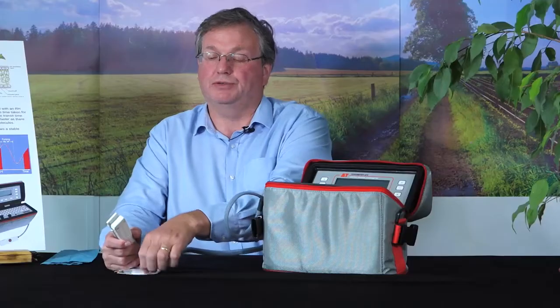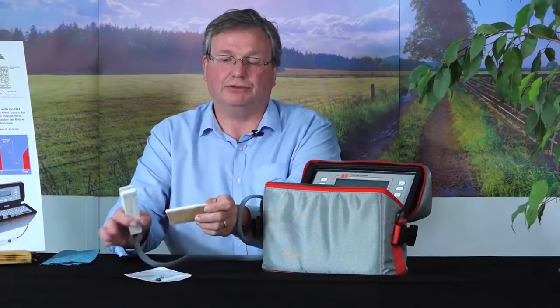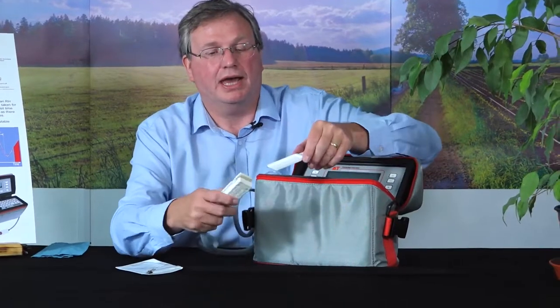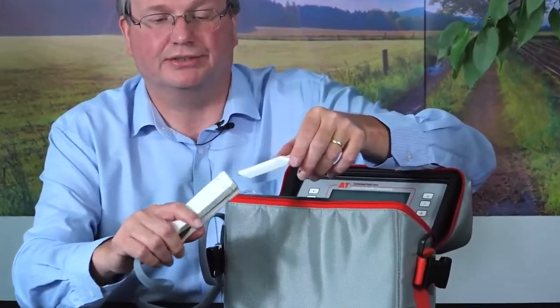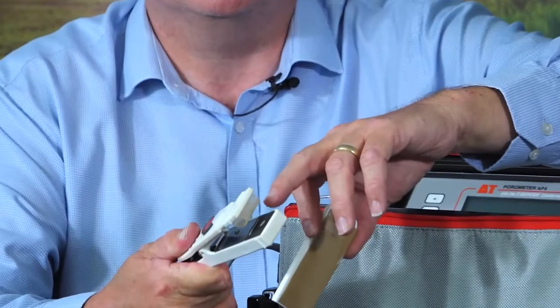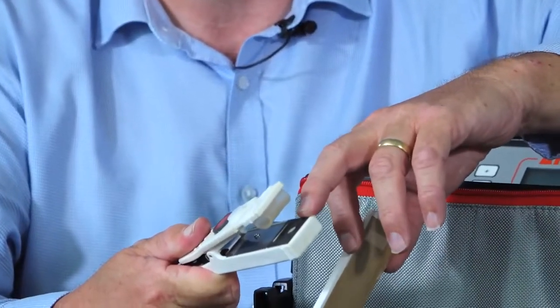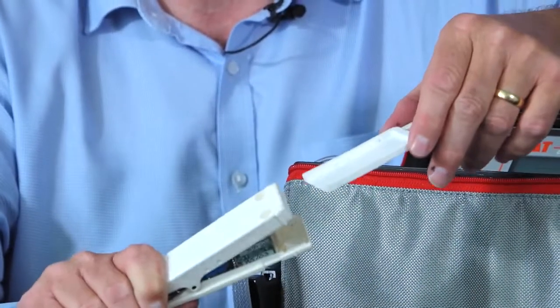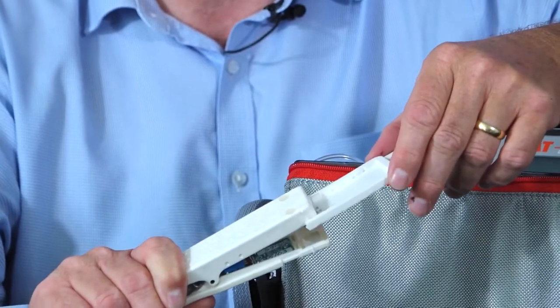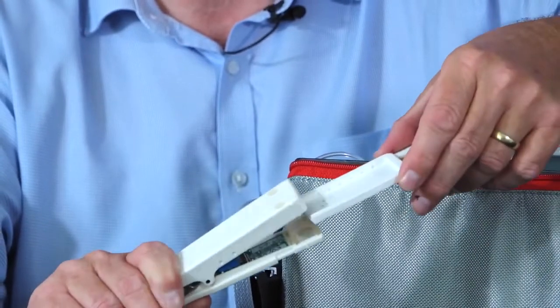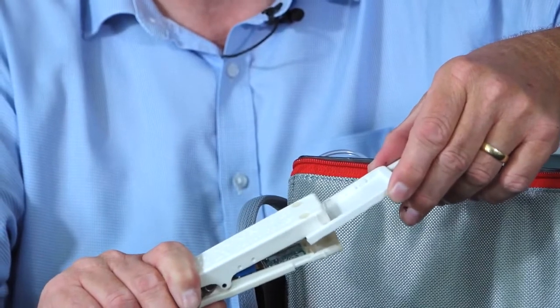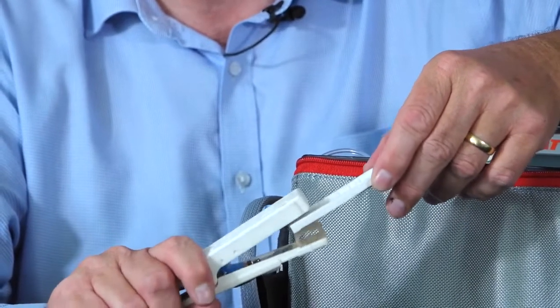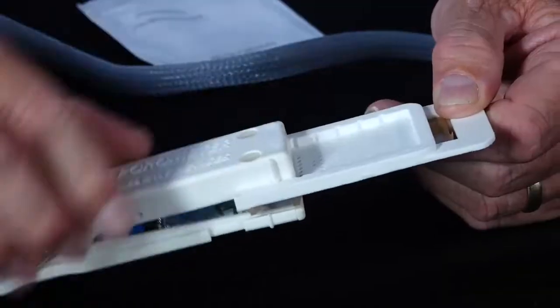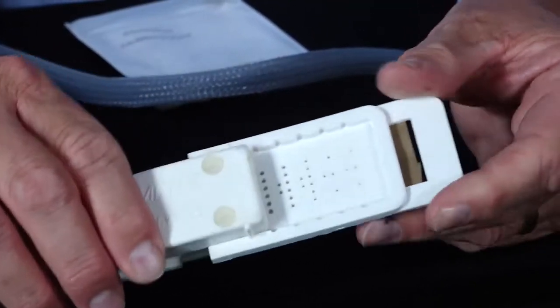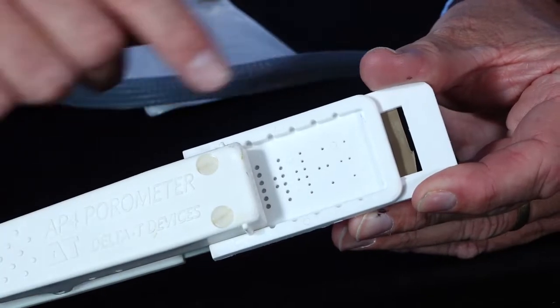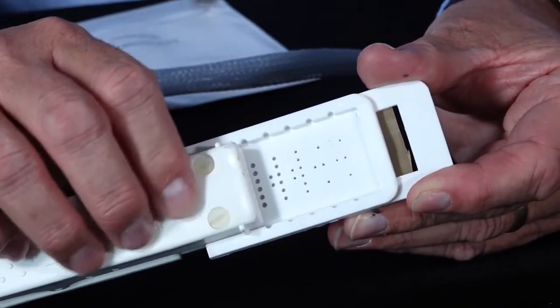So we need to move the calibration plate out of the pouch and we need to attach the head to position 6. We need to make sure that the measurement cup, which is on the underside here, around this black gasket, needs to be covering the holes in the calibration plate. So we go this way up. We need to position the plate into the head, and we're helped by these location lugs on the side of the head and the slots along the plate.